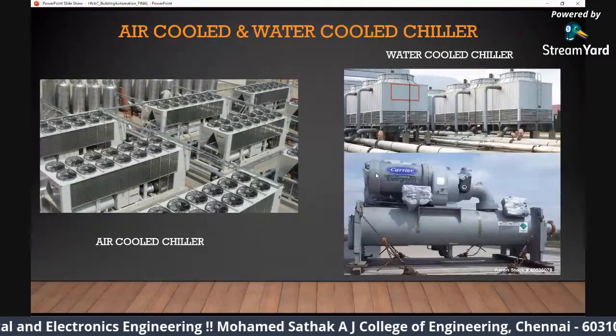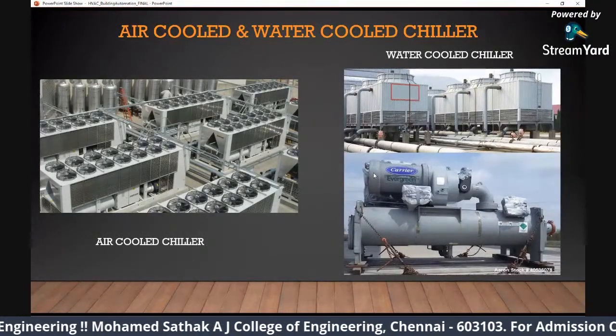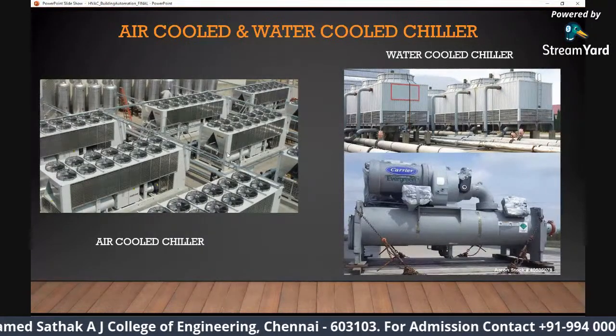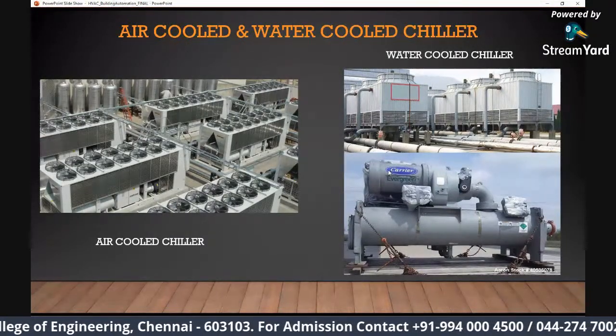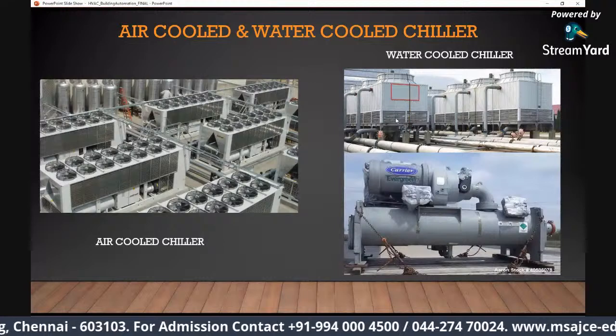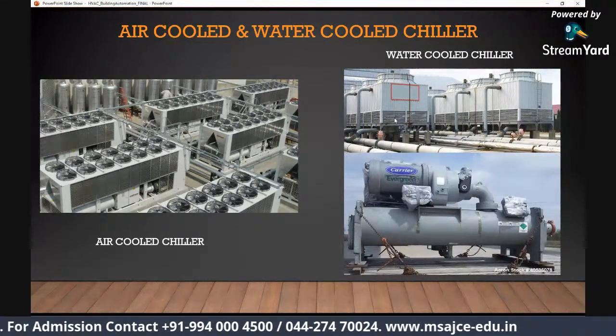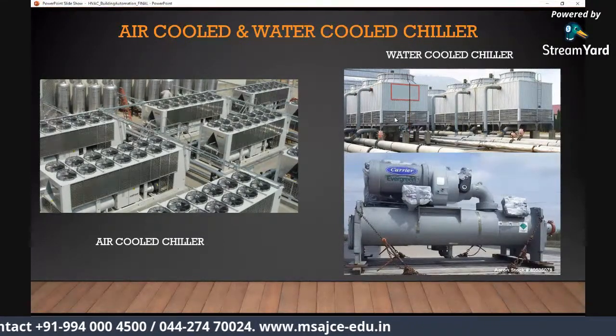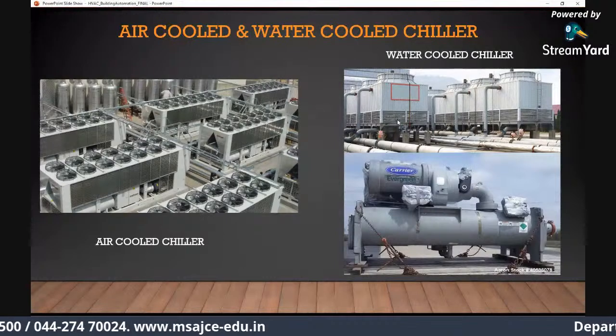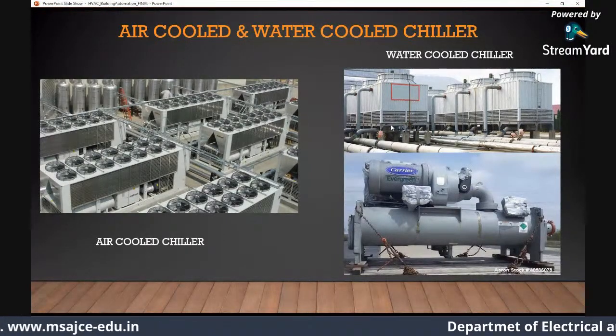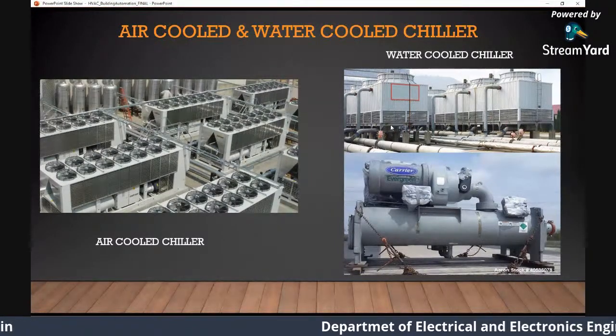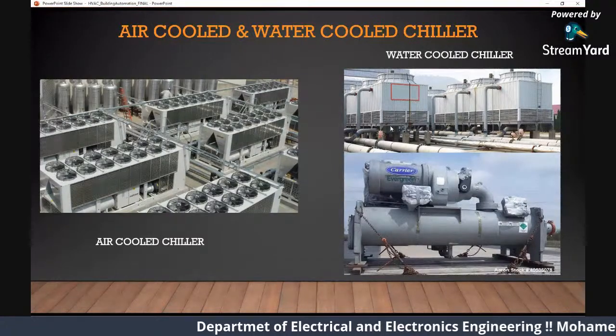If you see the Carrier picture, the one above, that's your condenser. The bottom one is the evaporator. If you put up multiple fans above the condenser part, it's called an air cooled chiller. If you have a cooling tower supplying water to cool the refrigerant in the condenser part, it's called a water cooled chiller. Only a water cooled chiller will have cooling towers. An air cooled chiller will not have a cooling tower. That's what I'm trying to get across here.